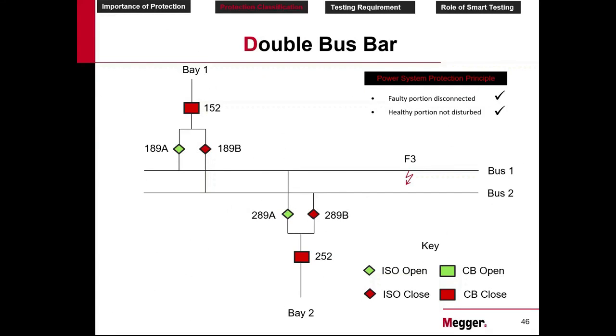It is for this reason that we need to have various bus arrangements. So we can see the need for double bus itself comes into the picture because of this power system protection principle. Single bus cannot satisfy this principle, therefore we have moved to double bus.